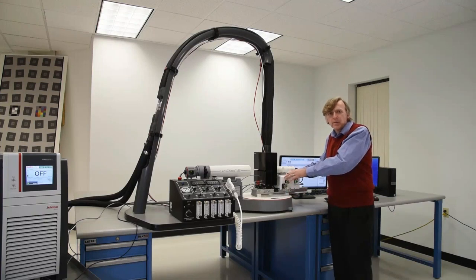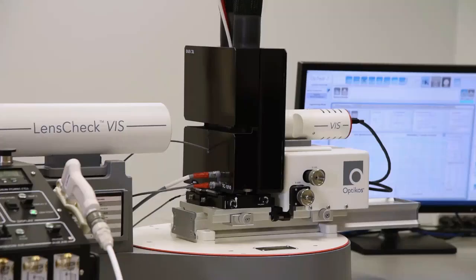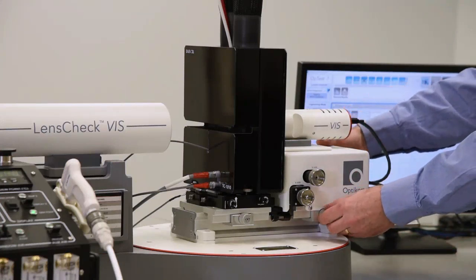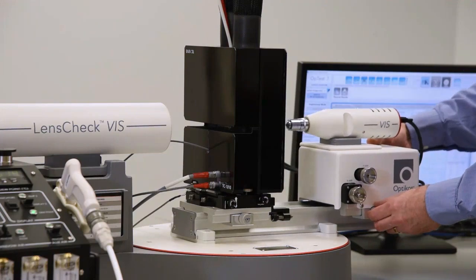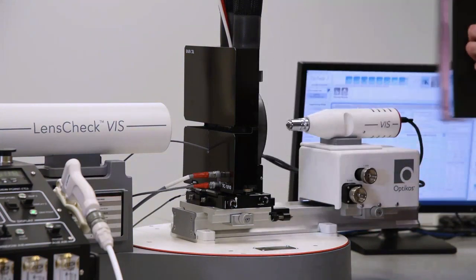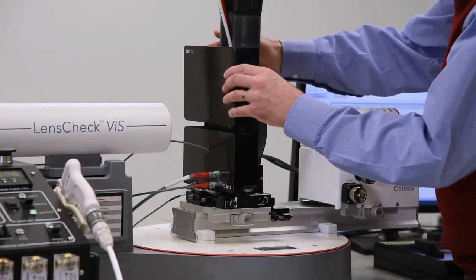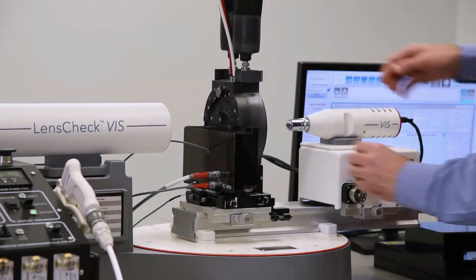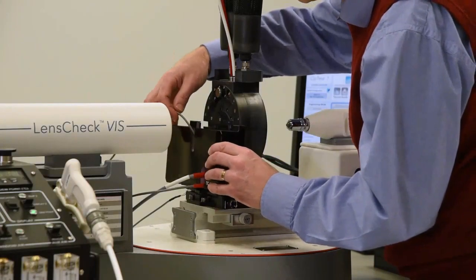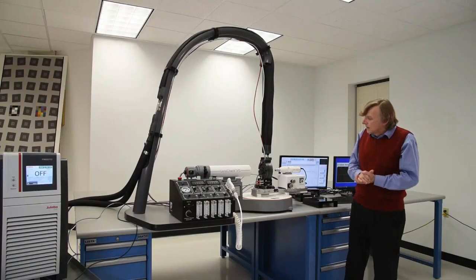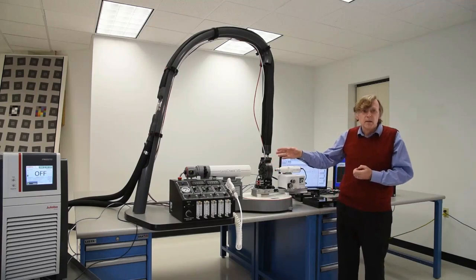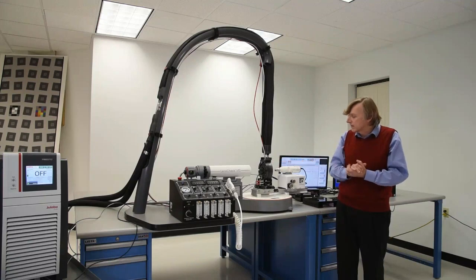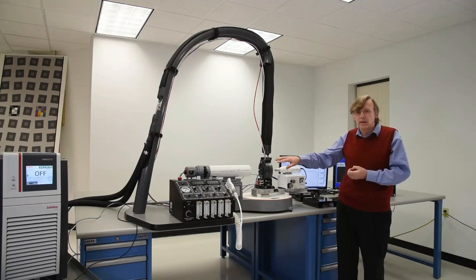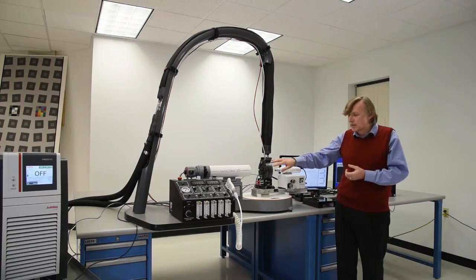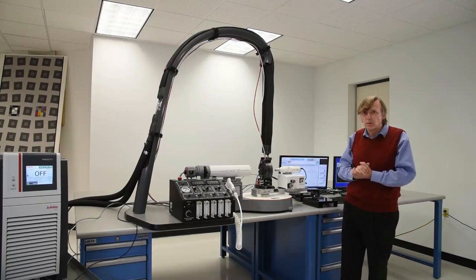Notice that I need to pull back the image analyzer to remove the back piece. But there is a finely adjustable stop in the base of the unit that allows me to return it to its previous position. We are now looking not at the heat exchanger, but instead at a hard shell that provides an additional layer of insulation and protects the operator from making direct contact with the heat exchanger. Of course, operators should always return the temperature of the thermal chamber to within a few degrees of ambient before opening it to retrieve or restore the lens.